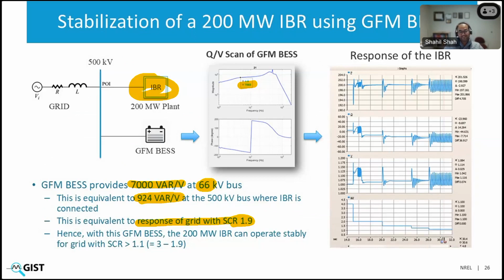So what it means is that with this grid forming BESS, our 200 megawatt IBR can operate stably with an SCR of 3 minus 1.9. So 3 is what is required, and 1.9 is coming from the grid forming BESS. So it needs only 1.1 SCR from the grid. So it's even better than our objective of stabilizing this plant at 1.5. And again, this is all using black box models, with no simplifying assumptions on the models of either the grid forming BESS or the 200 megawatt IBR.